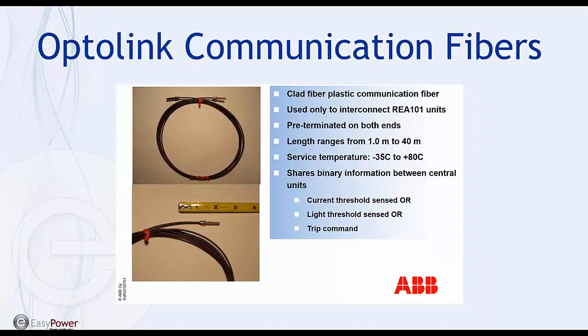Now we'll look at the OptoLink communication fibers. They range from 1 to 40 meters, and they're for connecting between the main units for transmit and receive current, light, and trip signals. The main units' voltage has to be at the same level for the communication to work properly.